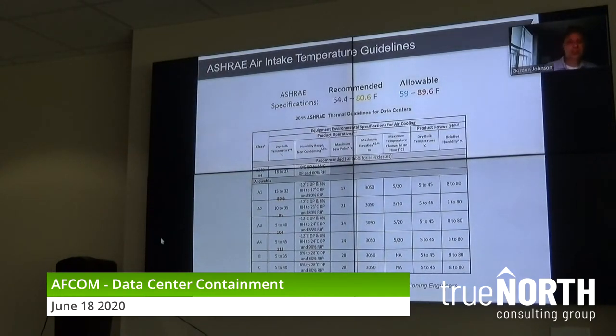Now, a separate discussion, you might be saying, is there a sweet spot where it's okay to run it higher than that, but I'm not really saving any money? The industry typically says 77 degrees. Then all your fans start ramping up on your IT equipment. But again, just for a definition, let's not go above 80.6 as your intake for your servers. Now, what happens if you're running everything very efficient, and you're at 75, 76, and a CRAC goes down, or two CRACs need to be serviced?